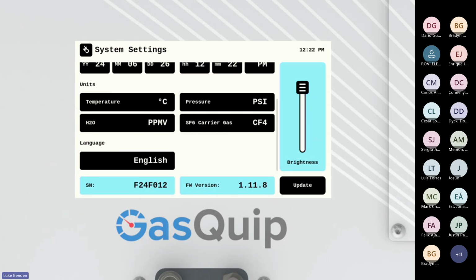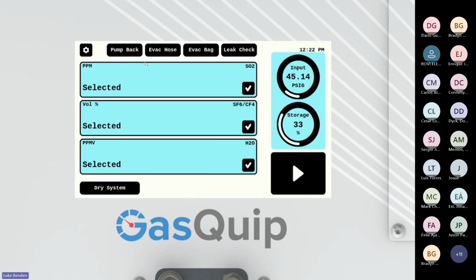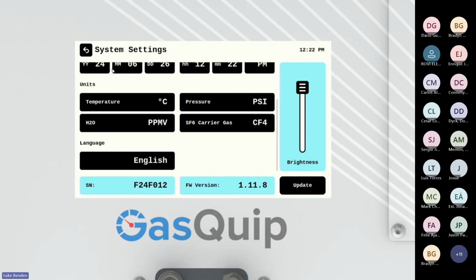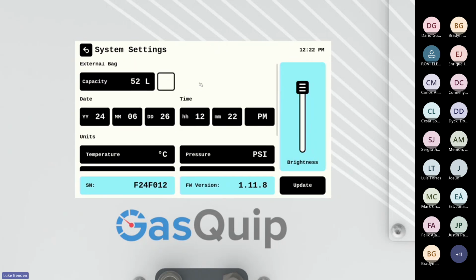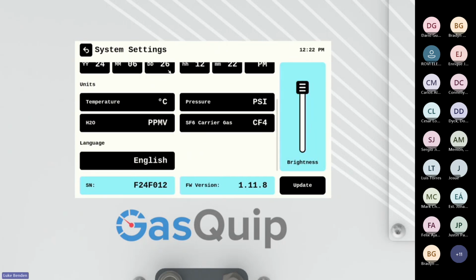So if we go back to our main screen, you'll see now that, where'd my mouse go? There it is. Our SF6/CF4 option here, and it'll spit out a result that has the breakdown of 60% SF6, 40% CF4 as that goes along. Something else I should point out here: the storage now jumped up to 33% because we don't have that external storage telling the system that we have external storage hooked up. So we'll leave that disabled, and obviously the language area there.